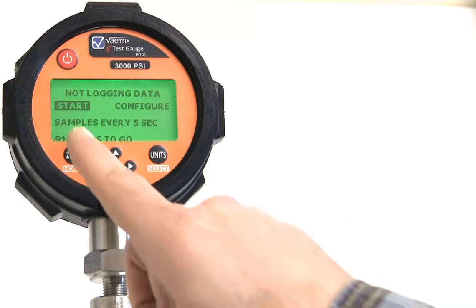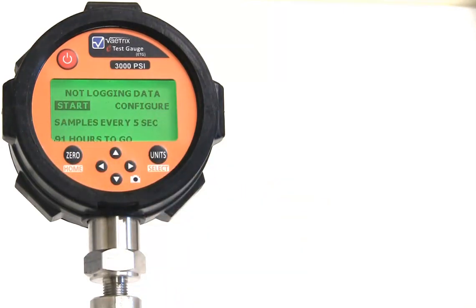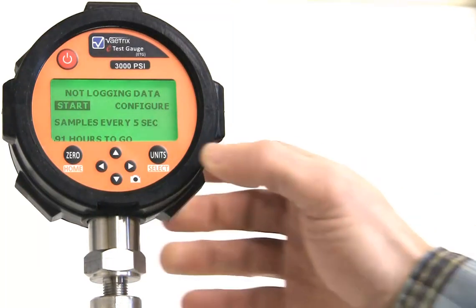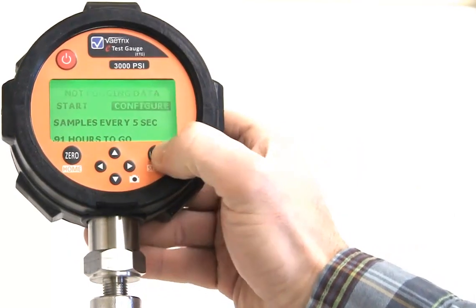It tells you the current sample rate that is set, samples every 5 seconds, and the amount of battery life that is left to conduct your test. So 91 hours to go, we could run and do data logging. So let's configure the device. Now, the ETG series does have the capability to store 200 sessions or 64,000 samples. So we're gonna set up the configuration.